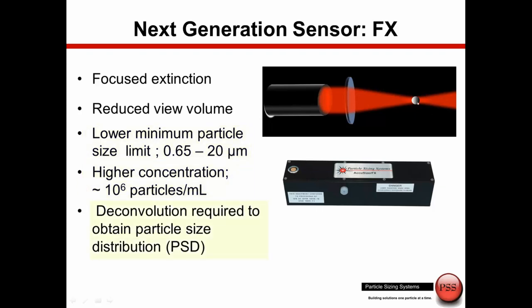Since we're focusing the laser beam, we're no longer inspecting 100% of the measurement zone. There is a deconvolution algorithm which takes the pulse heights and converts them into the particle size distribution of the particles in the sample.